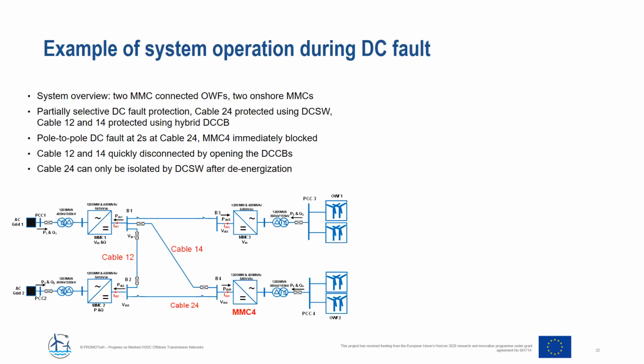To give an example, a 4-terminal DC network is considered. There are 2 onshore and 2 offshore converters connecting to offshore wind farms. Partially selective DC fault protection, as previously described, is used here. So cable 24 is protected using a DC switch, while cables 12 and 14 are protected using fast DCCBs.